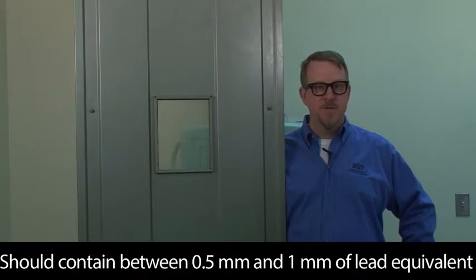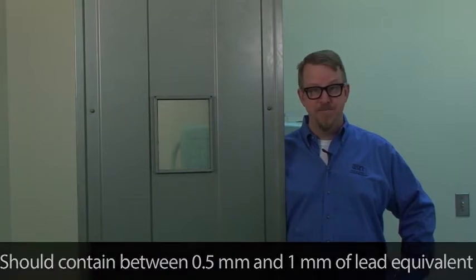These devices should contain between 0.5 millimeter and 1 millimeter of lead equivalent to absorb scatter radiation sufficiently. Mobile shields are particularly useful in the operating room when one diagnostic image is being taken, but they aren't very practical for use with the C-arm.